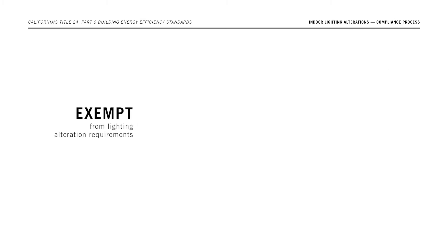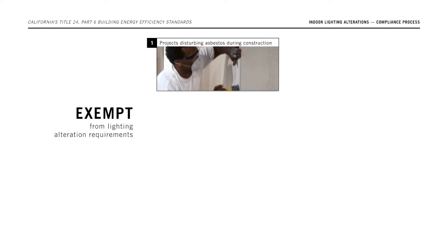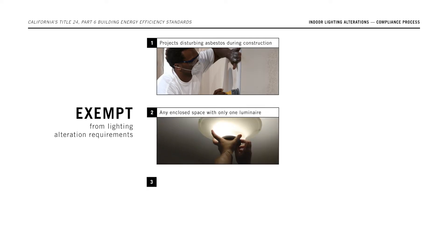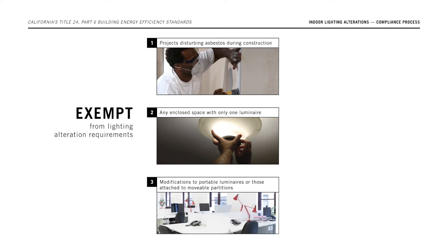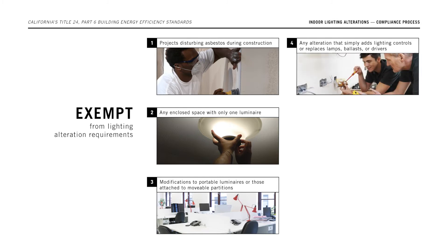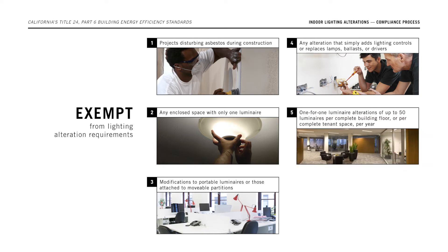Some projects are exempt from the lighting alteration requirements. These include projects that could disturb asbestos during construction; any enclosed space with only one luminaire; modifications to portable luminaires or those attached to movable partitions; any alteration that only adds lighting controls or replaces lamps, ballasts, or drivers; and one-for-one luminaire alterations of up to 50 luminaires per year per complete building floor or tenant space. Additionally, healthcare facilities using Option 2 or Option 3 are exempt from the shutoff control requirements.